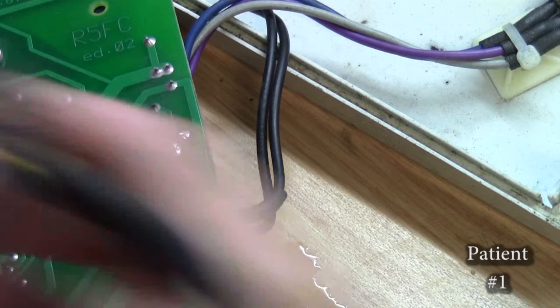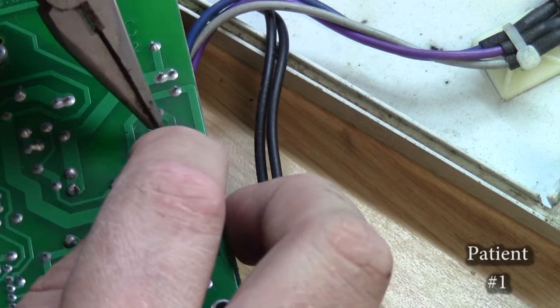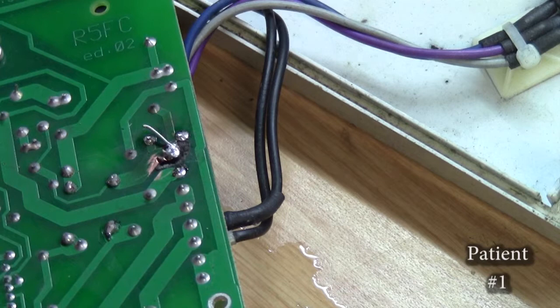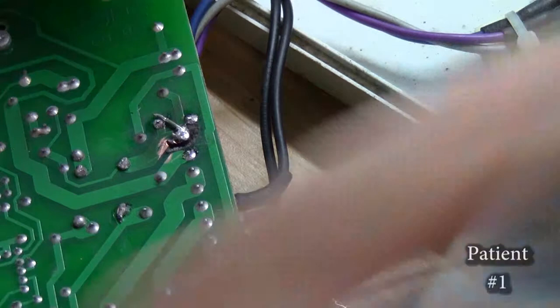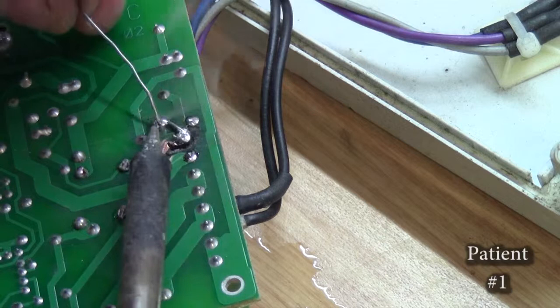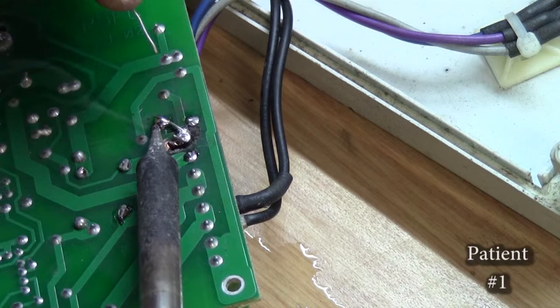I think this connection is quite loose. Oh, my pliers are a bit bent. This connection got loose for the terminal block, and it just vibrated itself to smithereens, and caused so much localized heat that it melted the solder for the capacitor. So we'll just secure that there. So now that's tied on. It takes a lot of heat.